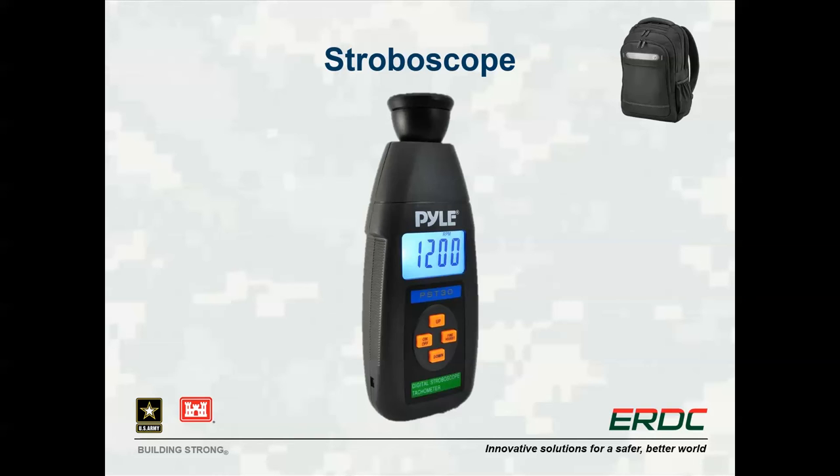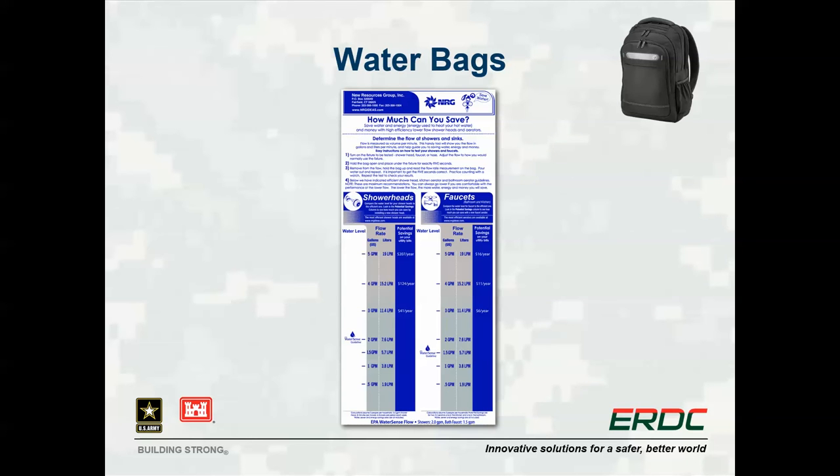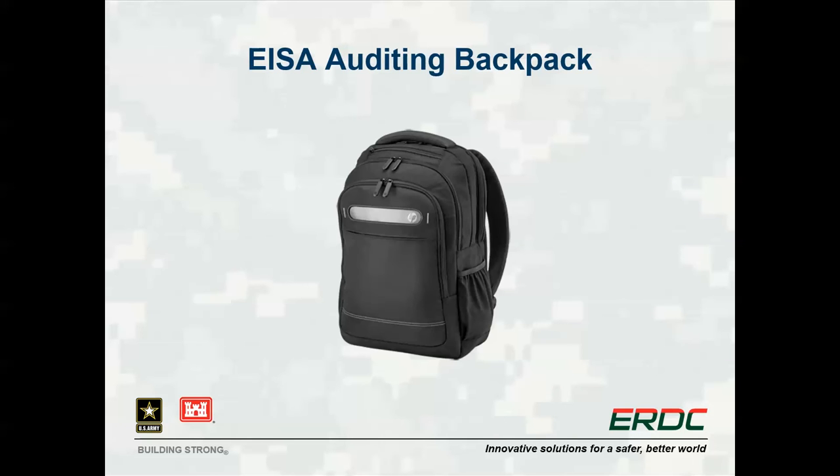The stroboscope can be used to determine the rotational speed of a motor, and from that speed you can estimate power usage using the slip method. These marked water bags can be used to measure flow rates for faucets and shower heads, with instructions on the bags, and can help determine expected water and cost savings potential when switching to the current recommended standard. That concludes the equipment contained in the EISA auditing backpacks. The additional equipment can be used for deeper study or to further explore issues found during the auditing process.